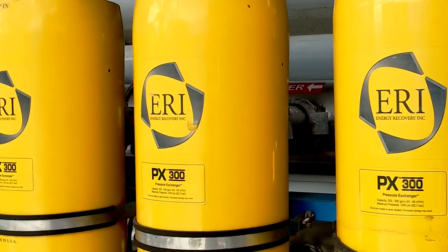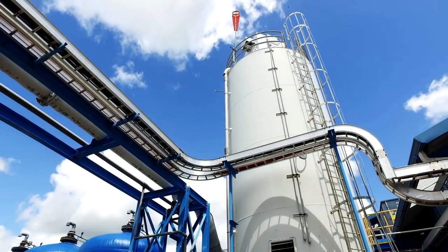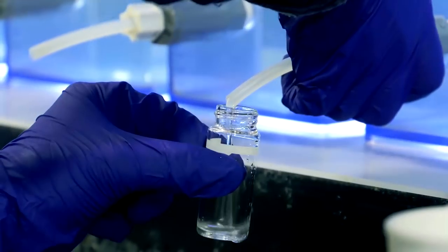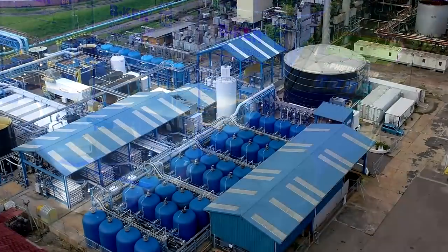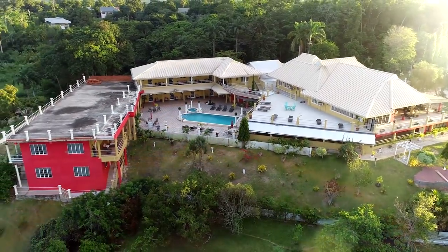This energy recovery system reduces the required reverse osmosis input energy by as much as 60%. After separation of the salts from the seawater, the permeate water is naturally balanced for taste and then transferred to the high-service storage tank. The finished water is continuously monitored to ensure the highest quality before being pumped under pressure directly into the water distribution system, delivering the water to over 40,000 people.